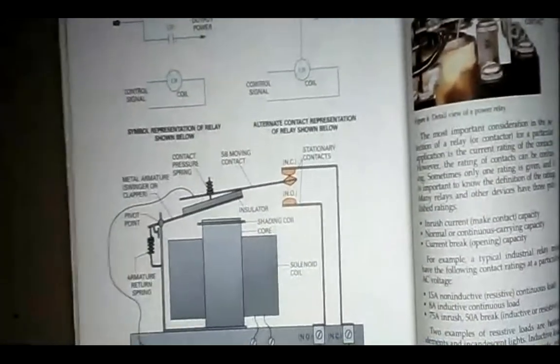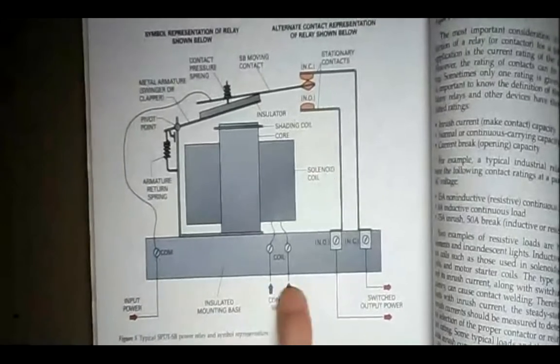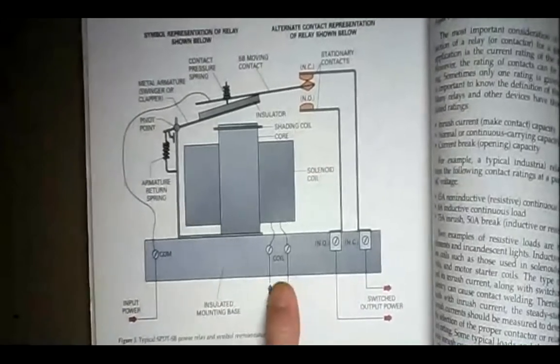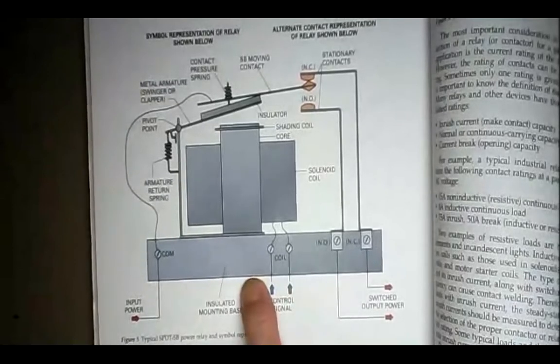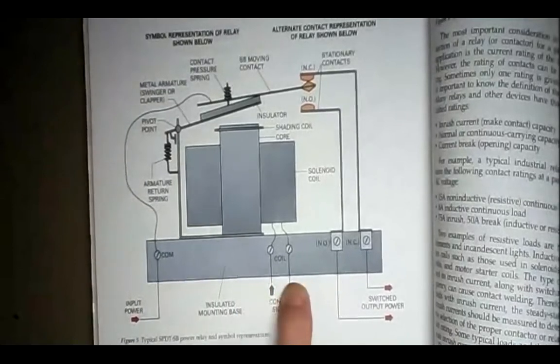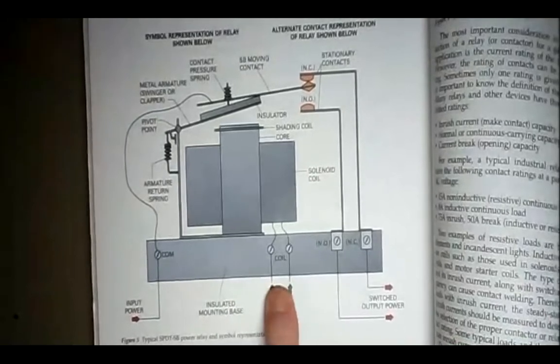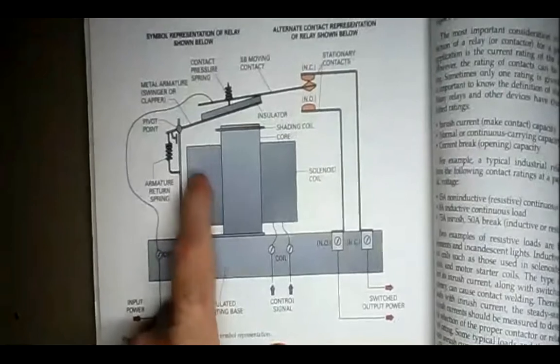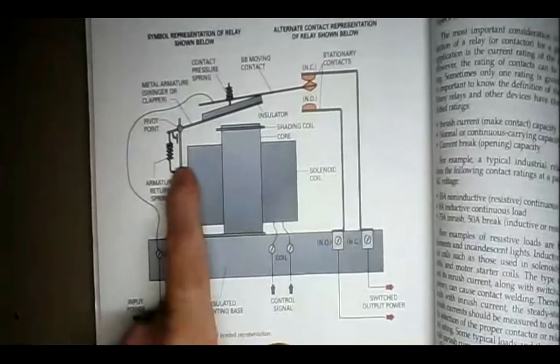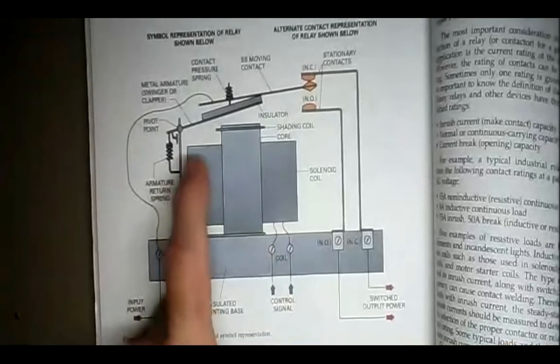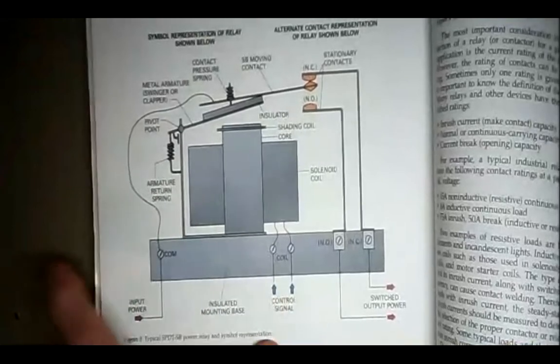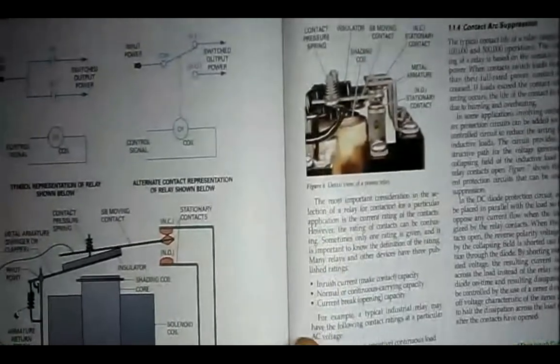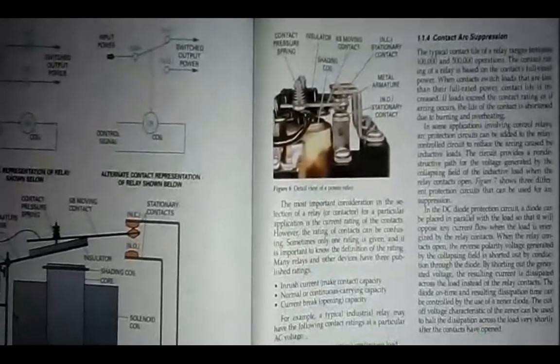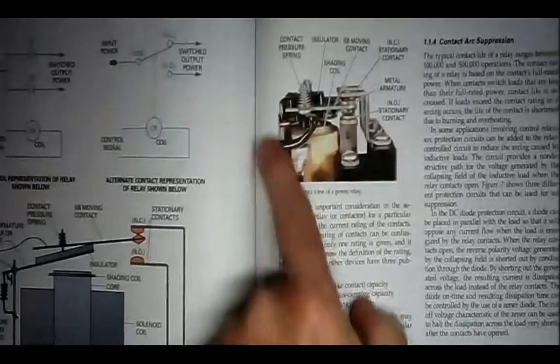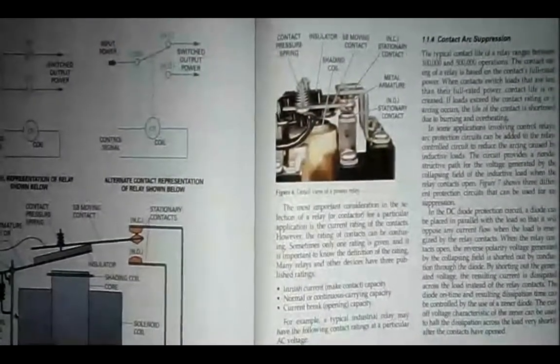The coil down here is actually what operates the relay, which makes it work. You can have a 12-volt coil or a 120-volt coil or a 480-volt coil. It all depends on what you're using it for. They have interchangeable coils. If you're changing out a coil on a motor starter, make sure that you're replacing one with the same voltage as the one you're taking out. You don't want to put a 120 volt coil in if they're using 240 volt control voltage. It'll burn up very rapidly. Okay, and there's just another example of those parts.